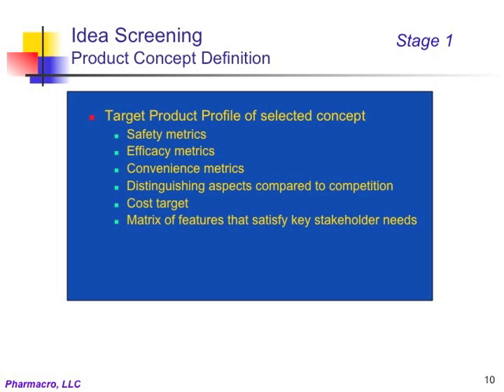After conducting market assessment and stakeholder analysis, the target product profile is defined. The profile will capture the requirements for safety and efficacy, which are the key criteria that the FDA considers during approval of a medical device. Also included in the product profile are requirements for convenient use, differentiating features of the product, the cost target, and a matrix of the needs of the key stakeholders and the features incorporated in the device that would meet those needs.